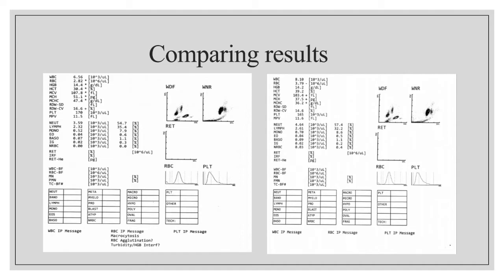In the case that you do get a much lower platelet count in your post-saline replacement printout, you will want to use the platelet result from the original printout.